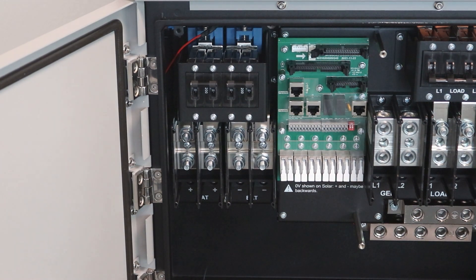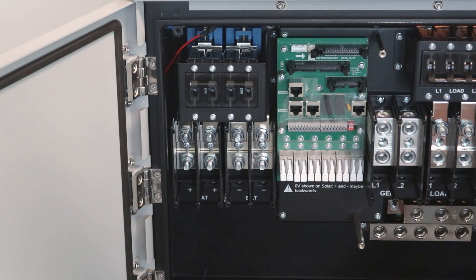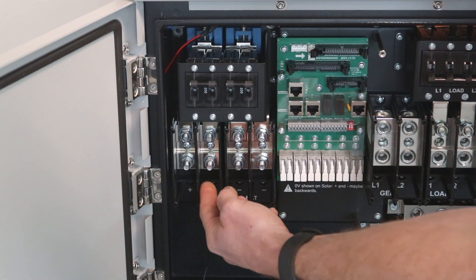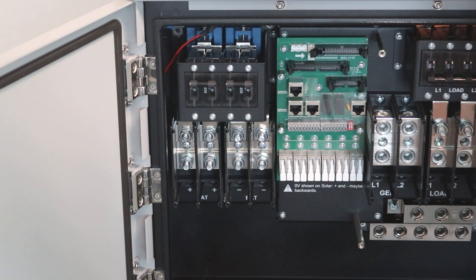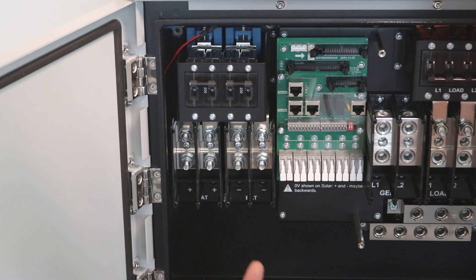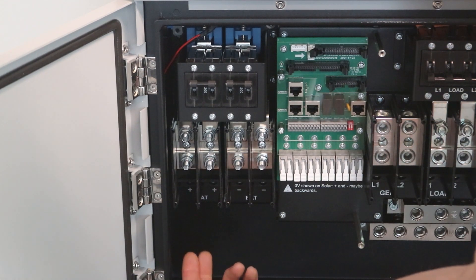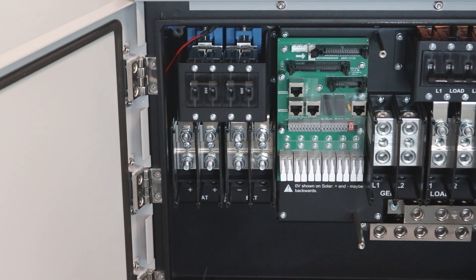Being that the HomeGrid battery is one of the only — if not the only — battery that can max out the specs on the Sol-Ark 15K inverter, we make a specialty bus bar kit that joins the two legs here. You run your 4/0 cable and connect the 15K bus bar kit. They come in pairs, so you'll have one for each your positive and your negative, and then you just run your 4/0 cable right into that bus bar. That joins the two legs so that way you can pull a full 275 amps off of the battery.